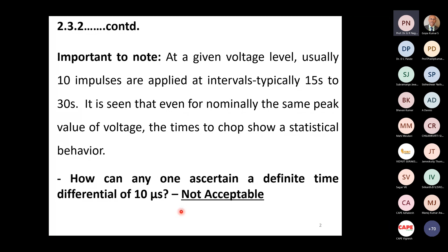Purely, remember, 100% purely on technical grounds which can be demonstrated in a laboratory. So now, yet another point. In the laboratory, a standard voltage wave with 1.2 microsecond front time and 50 microsecond tail time is used. This wave shape is generally shown there, but the front time can be 1.2 plus or minus 30% microseconds, that means it can vary from 0.84 to 1.56 microseconds. This is from laboratory to laboratory or setup to setup. For a given setup, it will be constant.